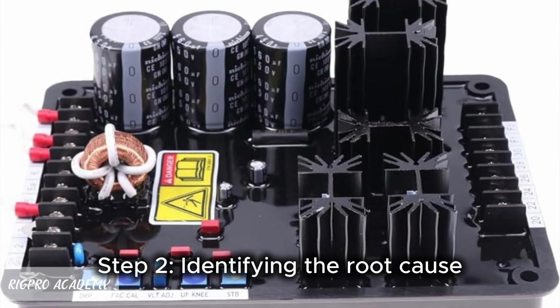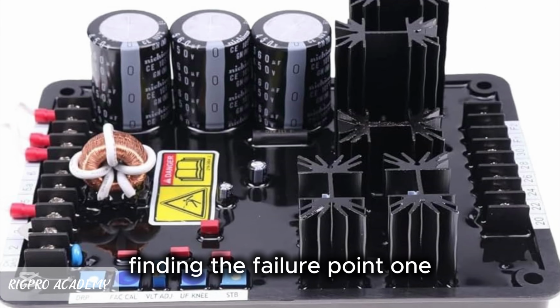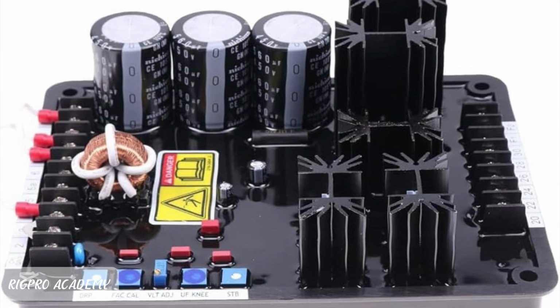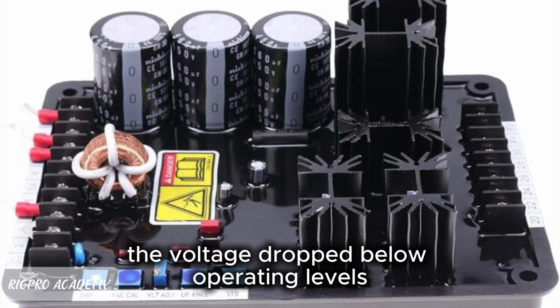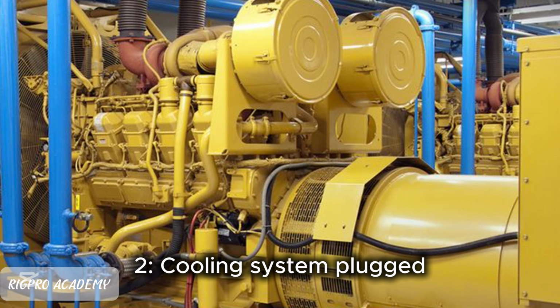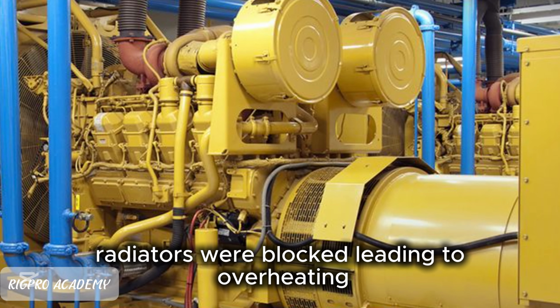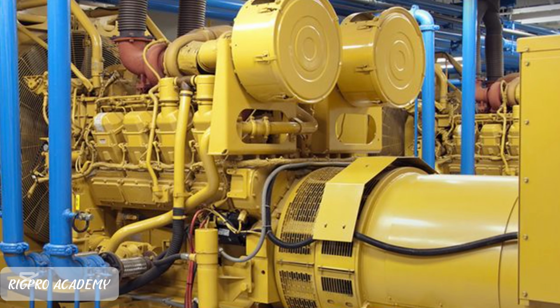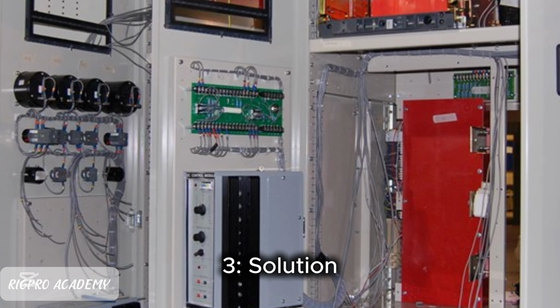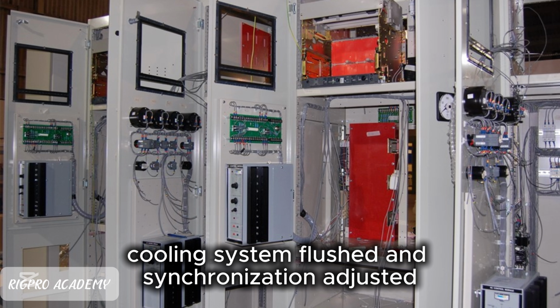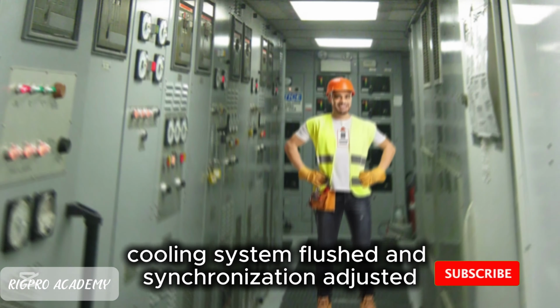Step 2, identifying the root cause. Finding the failure point. 1. AVR failure, the voltage dropped below operating levels, triggering a shutdown. 2. Cooling system clogged, radiators were blocked, leading to overheating. 3. Solution, AVR replaced, cooling system flushed, and synchronization adjusted.